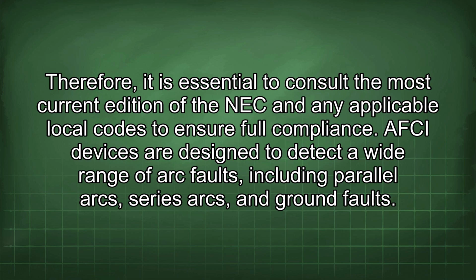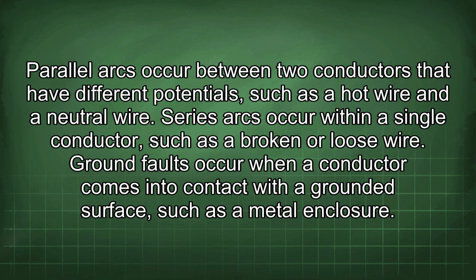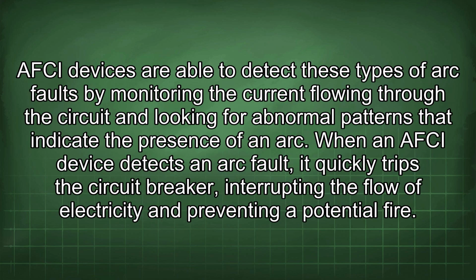AFCI devices are designed to detect a wide range of arc faults, including parallel arcs, series arcs, and ground faults. Parallel arcs occur between two conductors that have different potentials, such as a hot wire and a neutral wire. Series arcs occur within a single conductor, such as a broken or loose wire. Ground faults occur when a conductor comes into contact with a grounded surface, such as a metal enclosure. AFCI devices are able to detect these types of arc faults by monitoring the current flowing through the circuit and looking for abnormal patterns that indicate the presence of an arc.